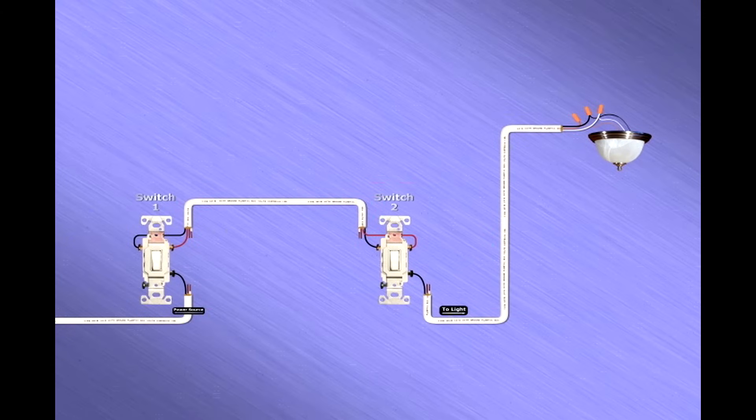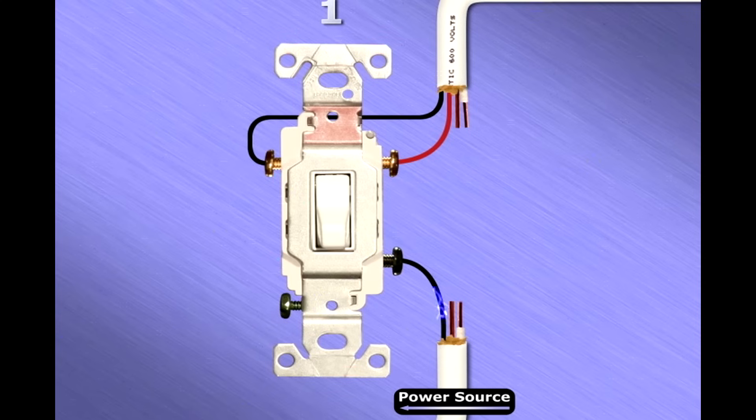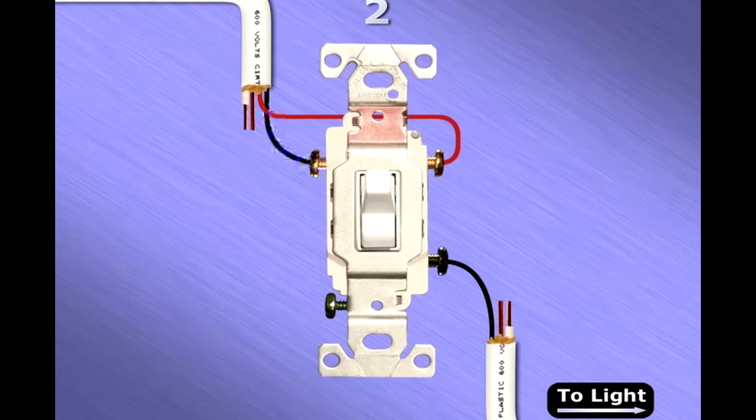Let's see how a three-way switch works in action. Electrical current travels from the power source and arrives at the common screw on the first switch. The current will either try to pass to the traveler screw on the left or the right. In our example, since the switch is in the down position, the current passes to the left traveler screw and travels along the black traveler wire until it reaches the second switch. If the second switch is in the up position, the current will stop — having nowhere to go — and the light will be off.